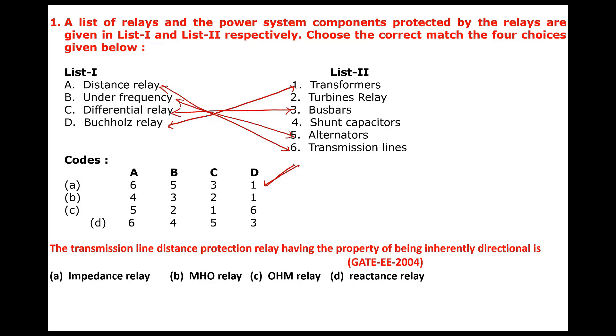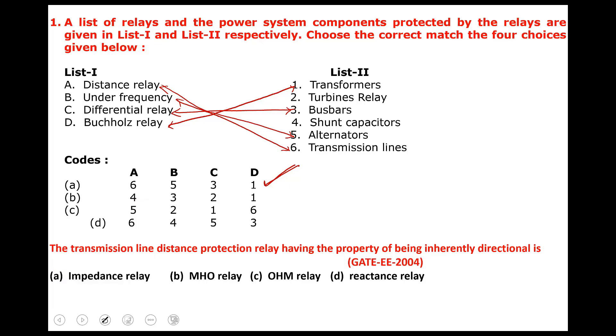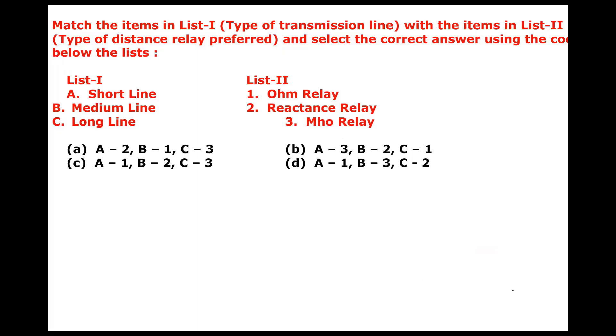The second question: in transmission line distance protection, which relay has an inherently directional feature? Mho relay is inherently directional. It is the only relay which is inherently directional, whereas all other relays — impedance relay, reactance relay, and ohm relay — are not inherently directional.